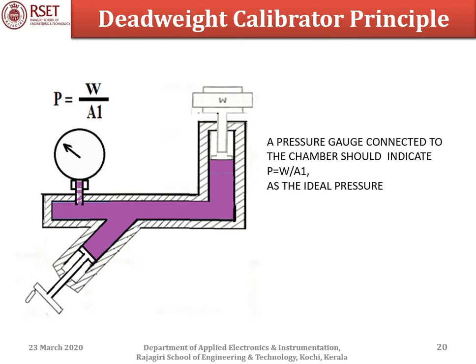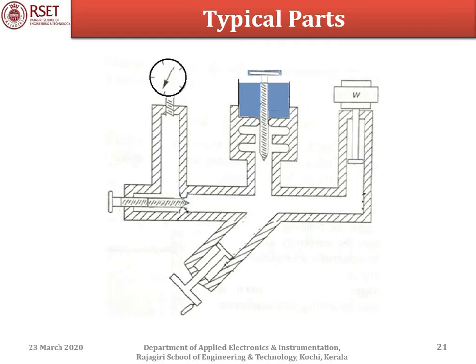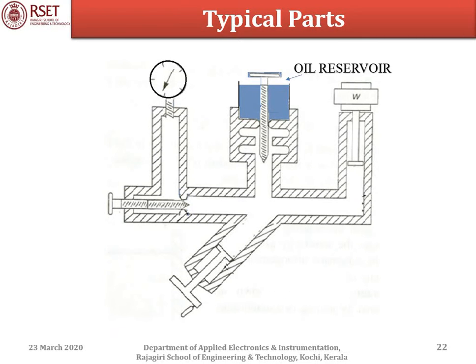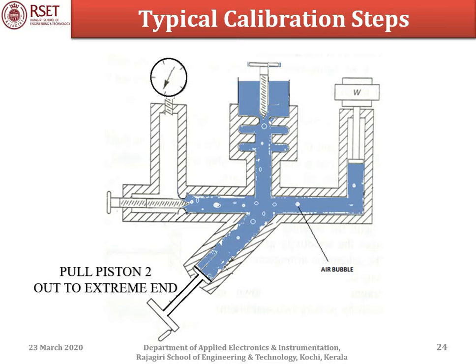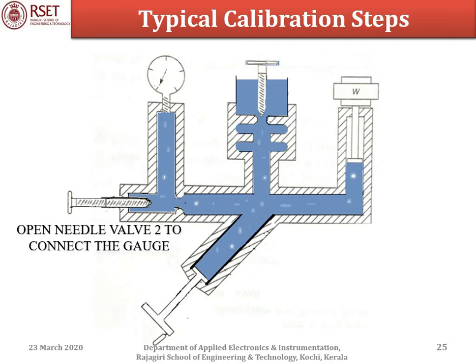Practical deadweight calibrators have additional parts. We have a gauge, piston 1, and piston 2. An oil reservoir supplies oil to the chamber when needle valve 1 is opened. Needle valve 2 is used to isolate the gauge tubing from the chamber. When needle valve 1 is opened, oil flows in; as piston 2 is pulled out, more oil enters. Needle valve 2 is then opened to connect the gauge. However, air bubbles may still be present, and to fully apply Pascal's law, these must be eliminated through a process called priming.